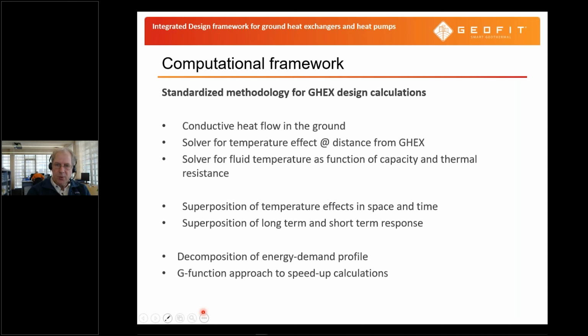The next thing was to have this standardized methodology for the ground source heat exchanger design calculations. We are mainly looking at conductive heat flow in the ground, so we're not considering groundwater flow. At this stage we're also not considering phase changes in the ground itself. Basically, what we did is develop a solver for temperature effect at a certain distance from the ground heat exchanger for all the different geometries that we have. And then we have a solver for the fluid temperature as a function of the capacity and the thermal resistance.